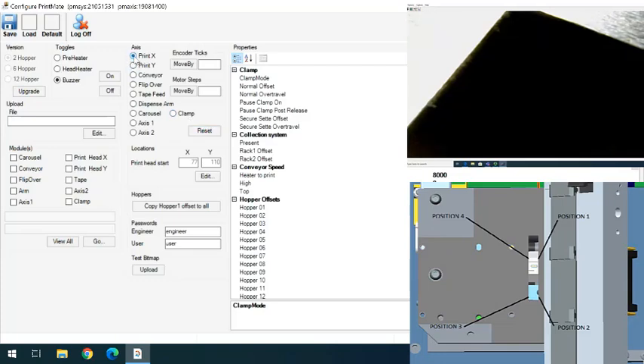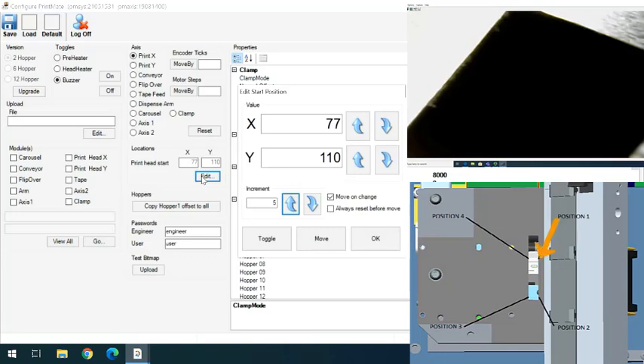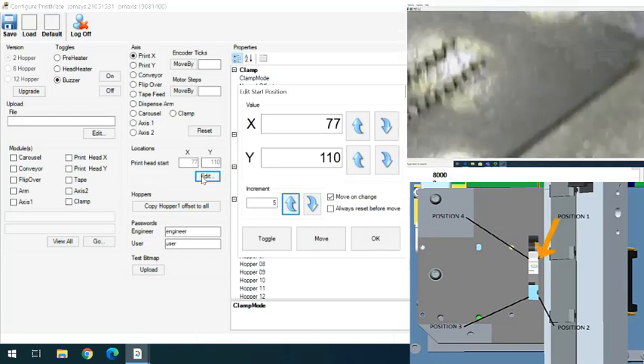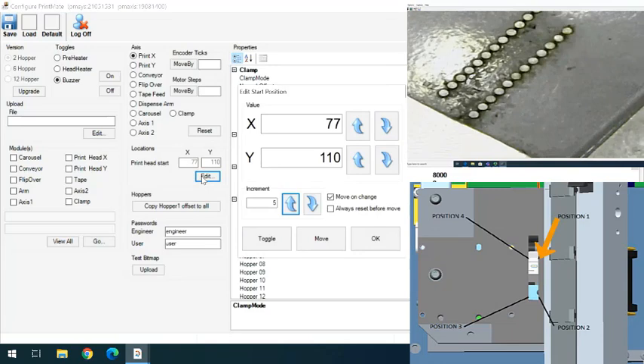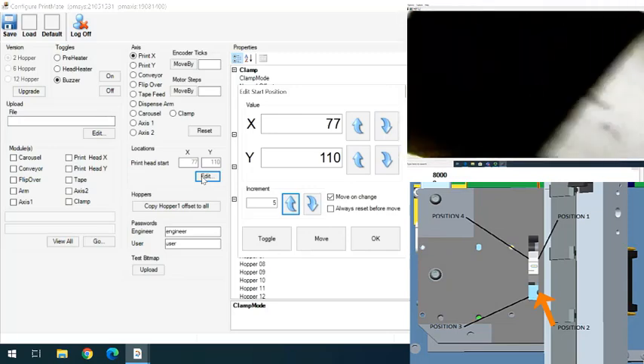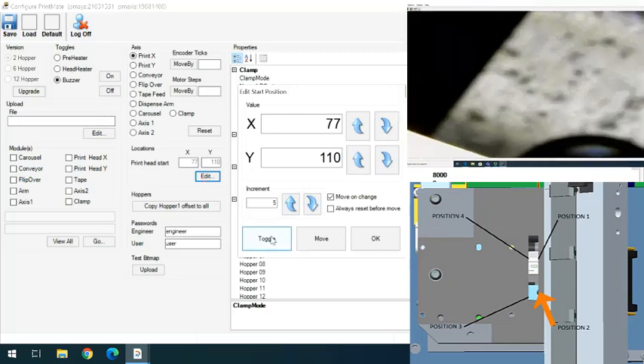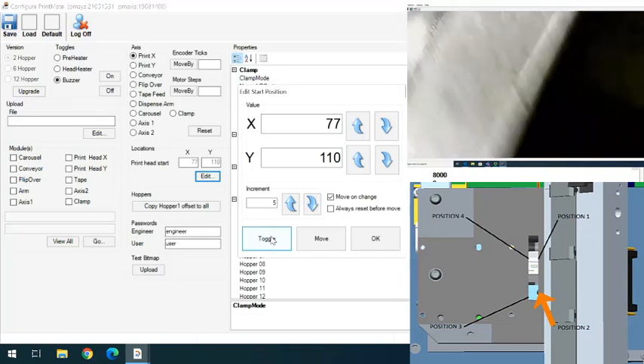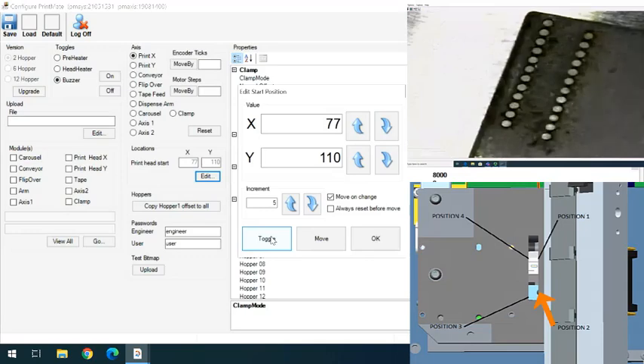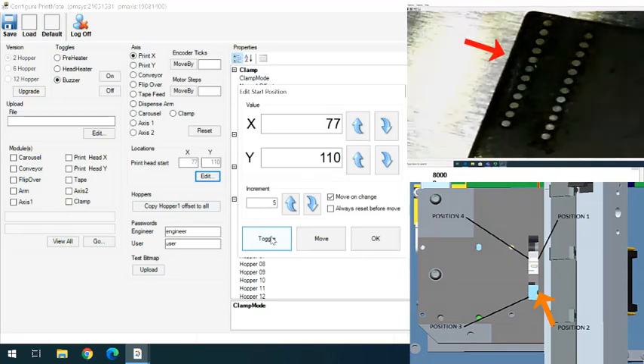reselect X, move to our edit window in locations, and check position 1. We can now verify position 1 on the Y axis is still calibrated. We see that the pin is still one pin width from the platen. We now toggle to position 2 and check our x-axis calibration. We come down to position 2 and we see that our x-axis is still one pin width from the platen.